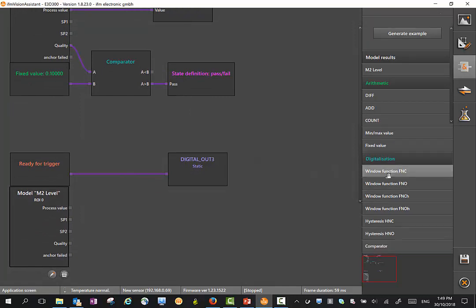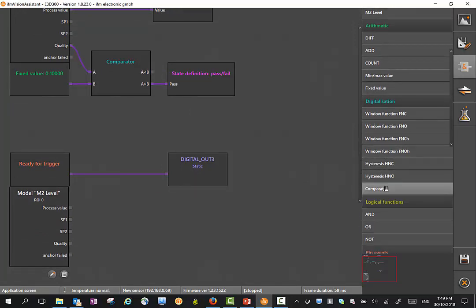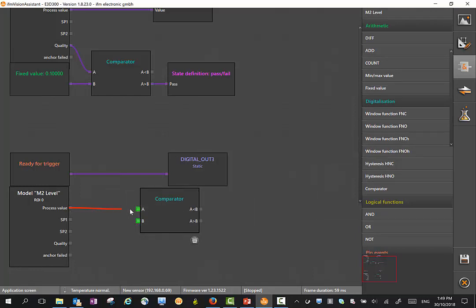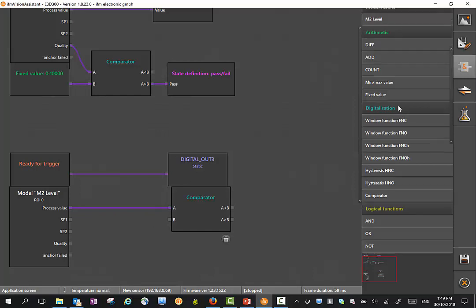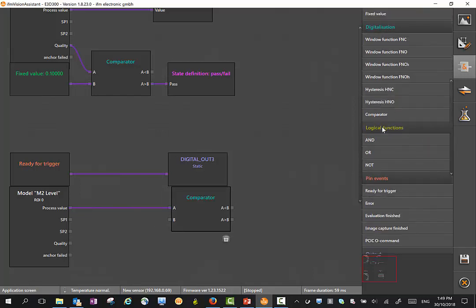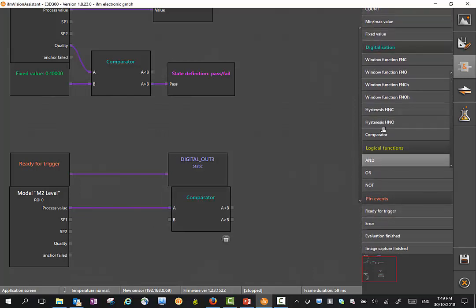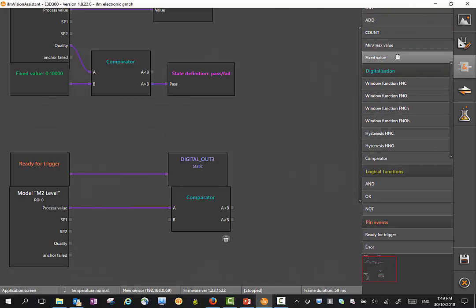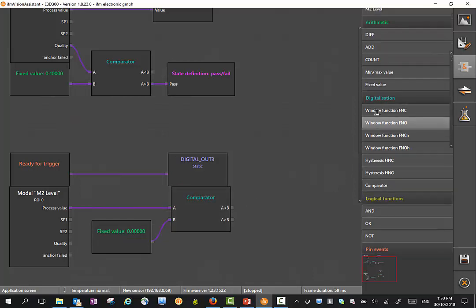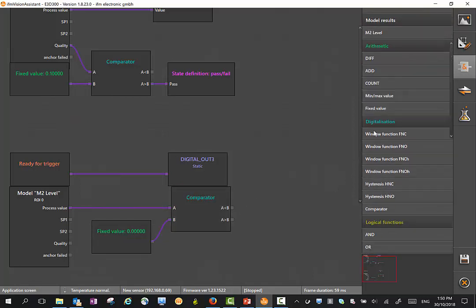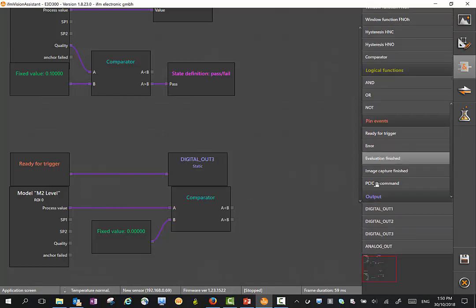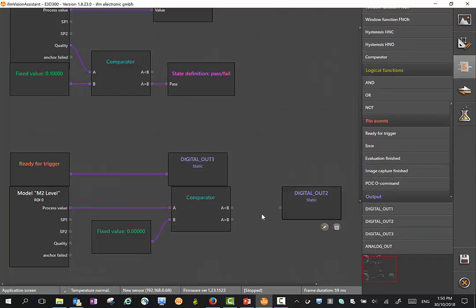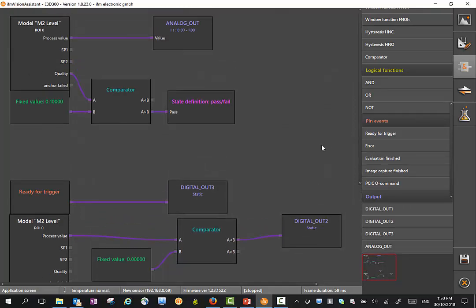For instance, if I want to, we could take a comparator here, take our process value to this point here and put in a fixed value, and simply drive output 2 from this. There are only three outputs, and please be aware that the analog output can only be used on output 1.